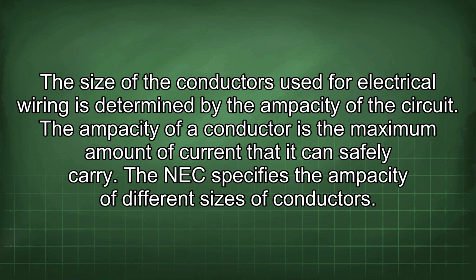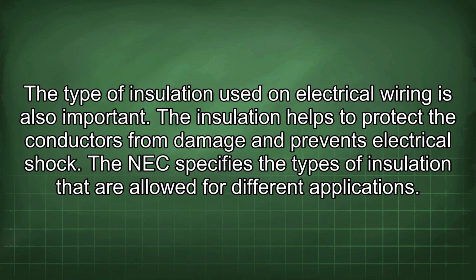The ampacity of a conductor is the maximum amount of current that it can safely carry. The NEC specifies the ampacity of different sizes of conductors. The type of insulation used on electrical wiring is also important. The insulation helps to protect the conductors from damage and prevents electrical shock. The NEC specifies the types of insulation that are allowed for different applications.